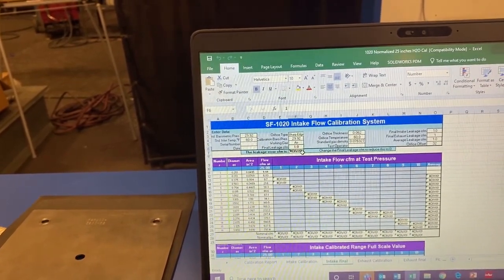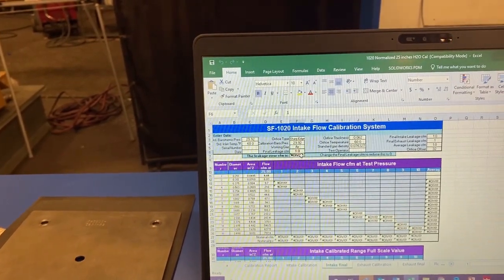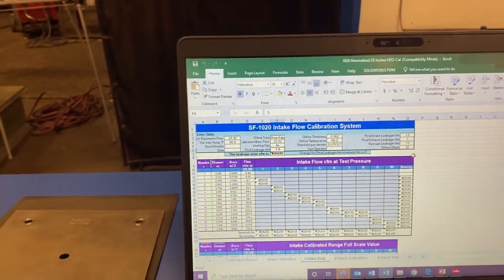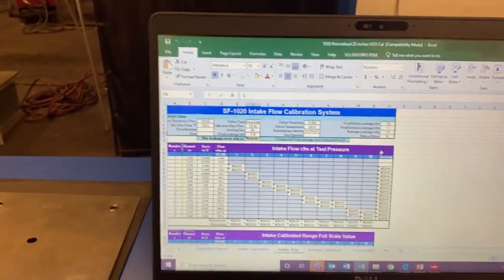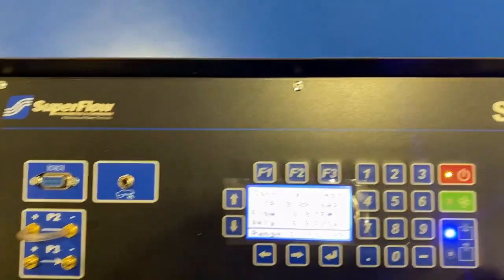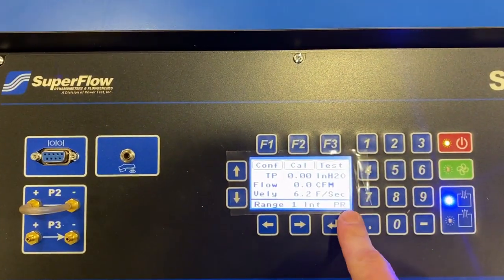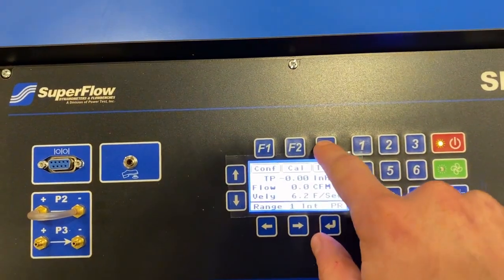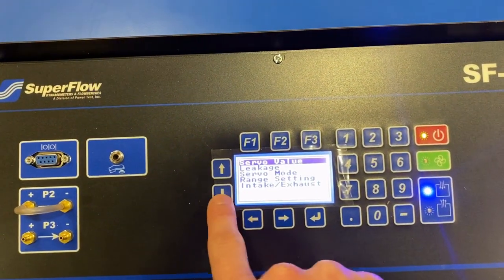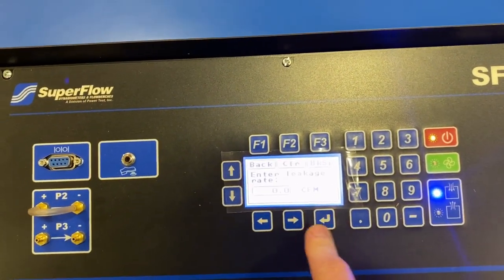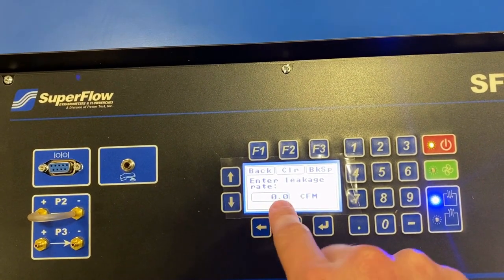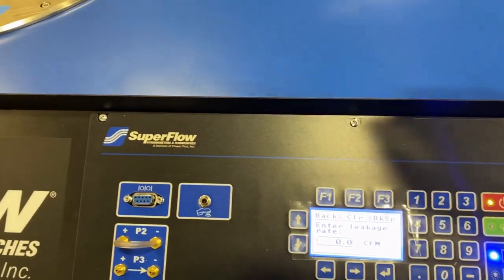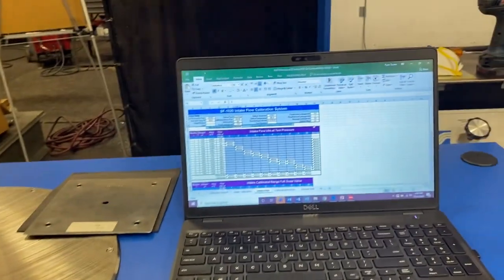You can see that right now we have a value of 1 in there, which suggests there's 1 CFM of leakage in this bench. Now, that's not actually true, because this bench has a leakage of 0.5 from testing it earlier. But we also want to make sure that while we're testing this leakage, this value is 0. The leakage value in the bench has to be 0 for us to get an accurate reading for the leakage for the Excel sheet.